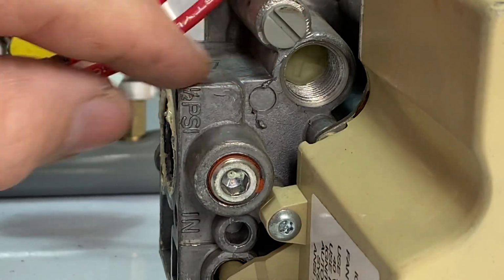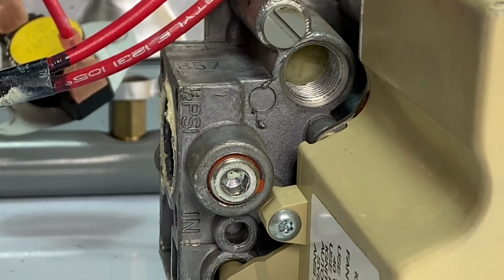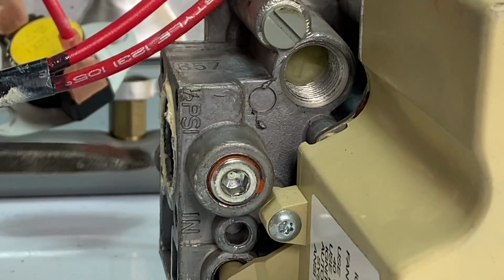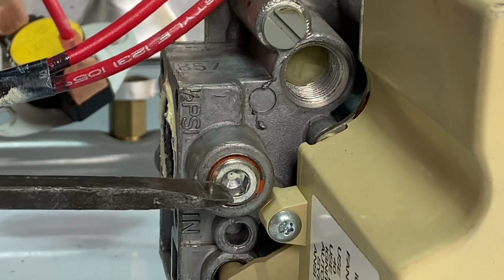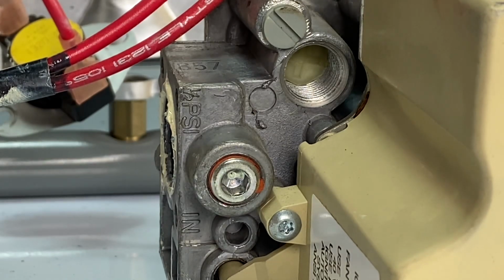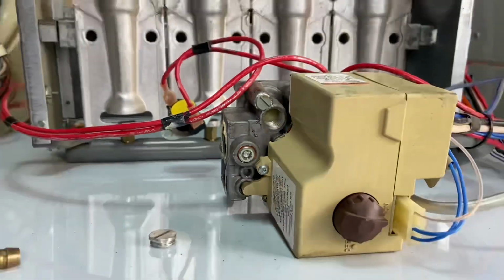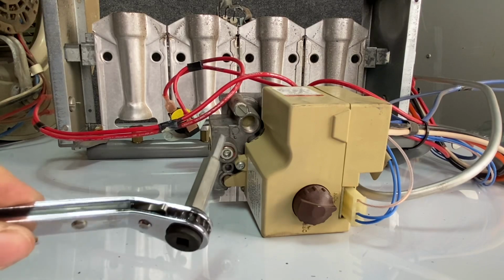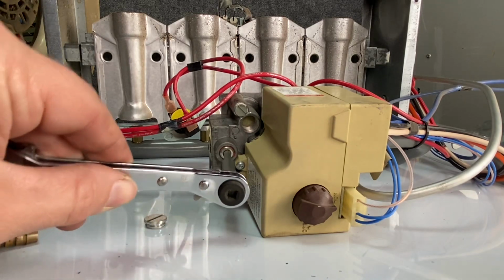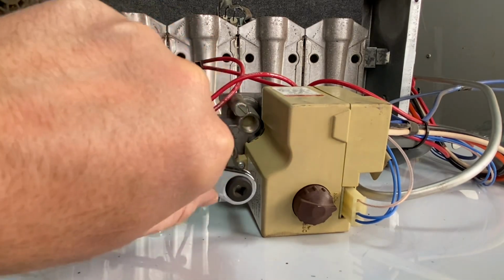On the side port here, that was usually for our pilot assembly, so we could adjust the flame on our pilot assembly. Also, you see here it has our PSI. This is our inlet. This is the adapter where we can check the gas pressure coming into the gas furnace, and we want to check that static and while it's working. We have a tool that we use for that. It's the same tool we use for AC. It's our service wrench, and that same adapter fits into that, and we'd set this to be loosened.